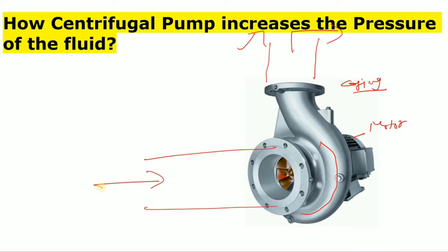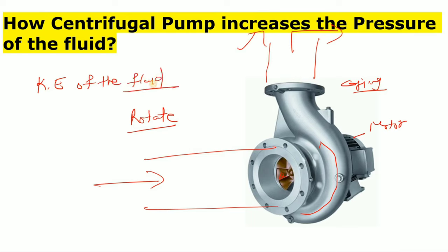The fluid will come in from here — there will be a strainer and a valve, though I am not drawing those here. When we start the centrifugal pump, the impeller will rotate. As the fluid goes through the eye of the impeller and the impeller rotates, it will increase the kinetic energy of the fluid. At the eye of the impeller, it will create a vacuum.